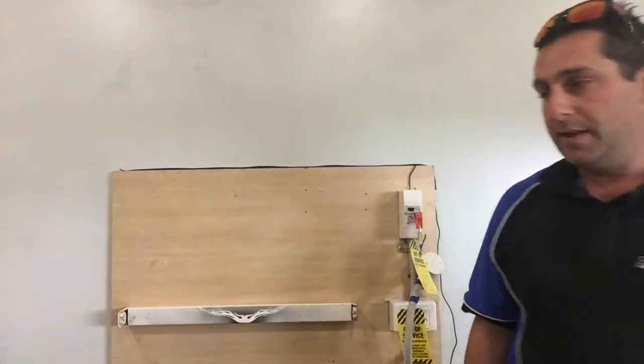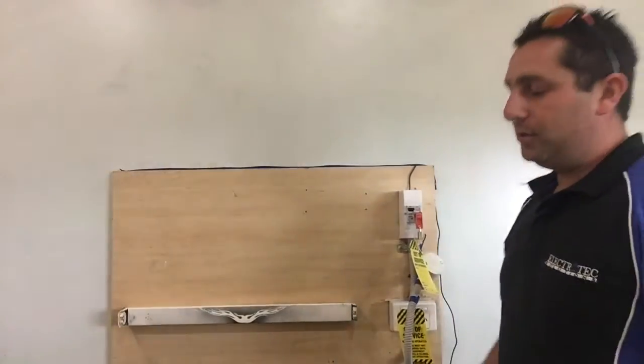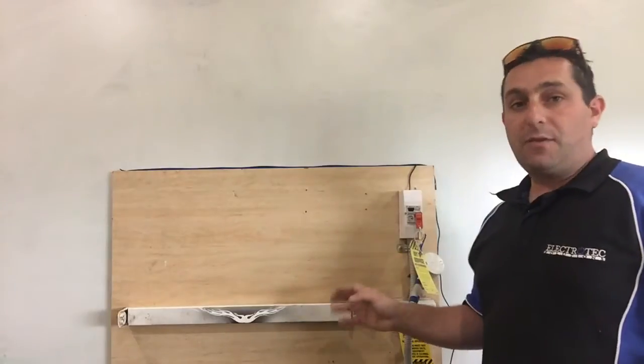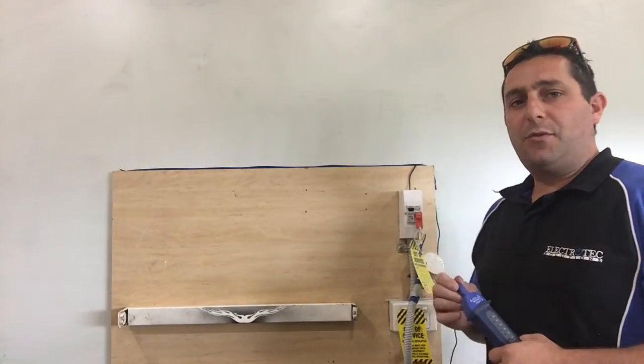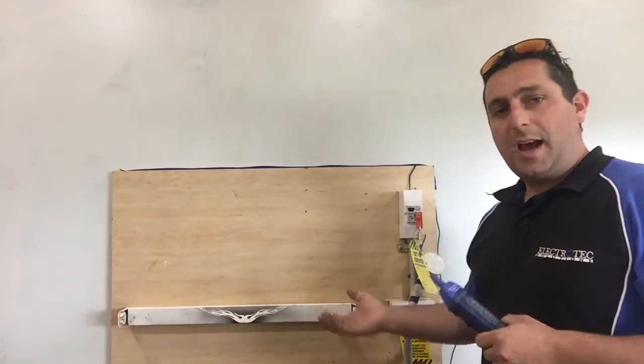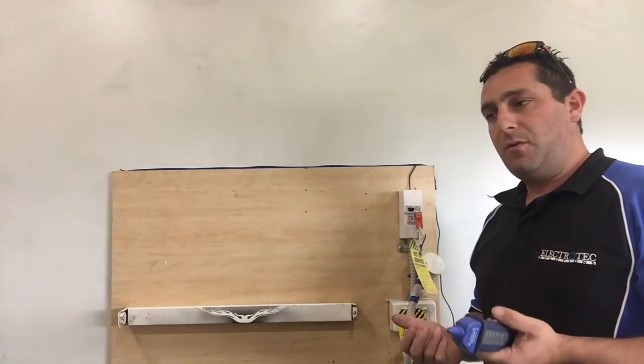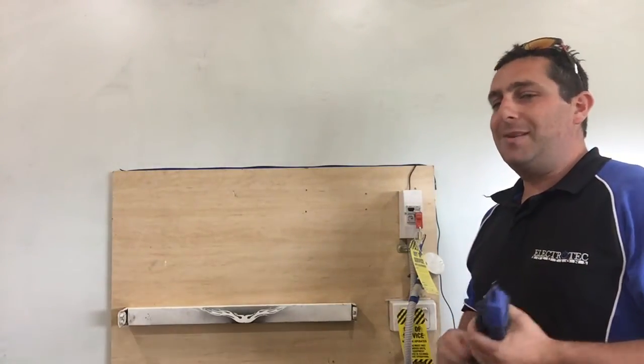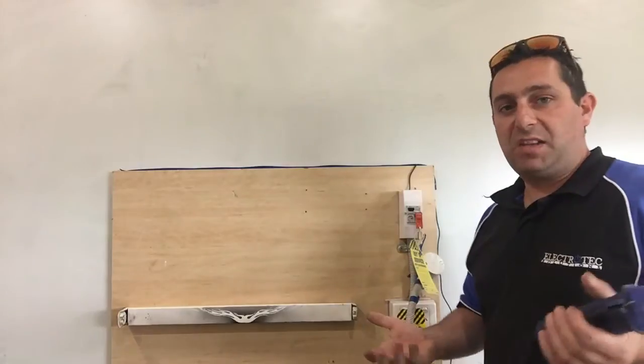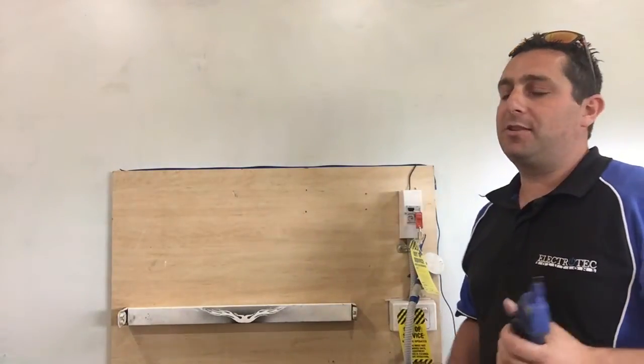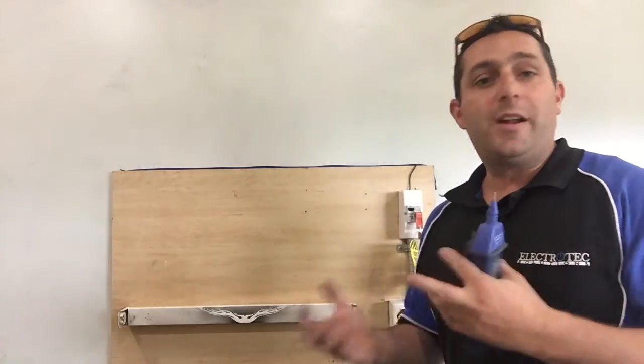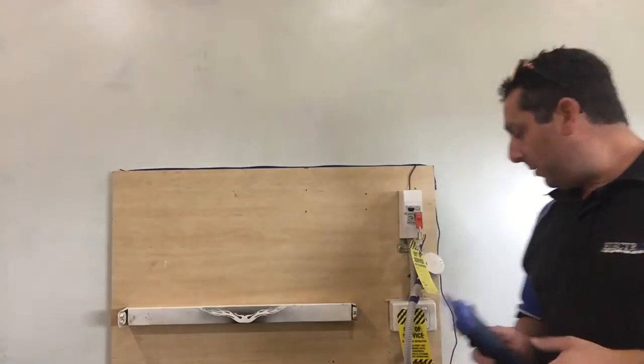Okay, so we've been told that the appliance has been fixed, repaired. We've just carried it back in, we've screwed up, we might have done whatever that might need to be done. It's not necessary to test the frame now, because if you remember we said that at the start we didn't want to go touching anything before we checked for stray voltages. In theory, we've just carried this in, there's no electrical connection, so the book says that we don't have to test it. I don't completely agree with that.